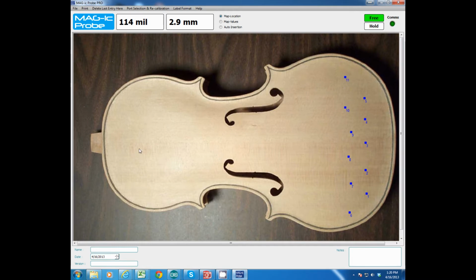Once you're ready, of course, you can fill up the whole instrument with pre-planned measuring spaces, and once you're ready to actually measure, you change at the top to map values. What will happen with the map values is that the current reading will be transferred to location number 1 as soon as I click the mouse. Now I don't have to click it anywhere particular on the screen. I can click the mouse anywhere on the screen, and that value will be transferred to location number 1. You'll see 2.9, and every time I click the mouse after that, the current reading will be added to the next sequence of locations. So this is my next reading over there. I click my mouse and that value gets entered in number 2, and then number 3, and so forth as I go about my measurements.